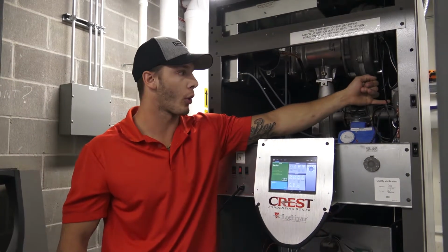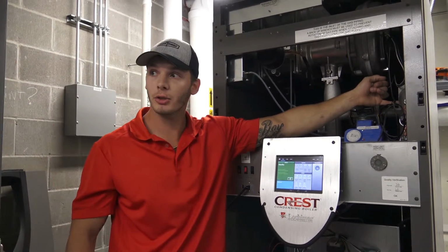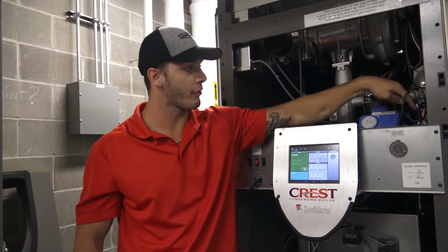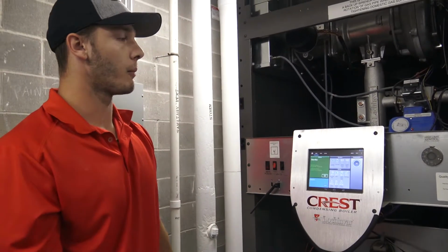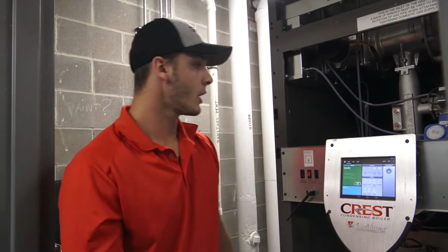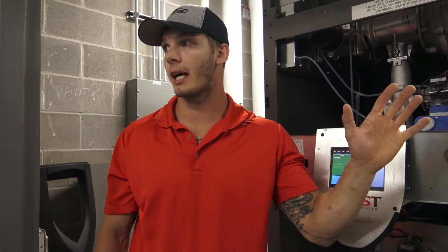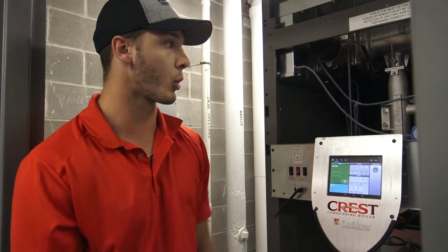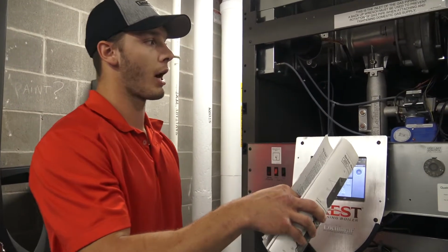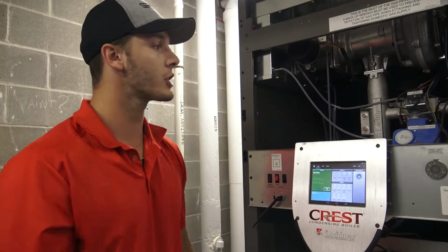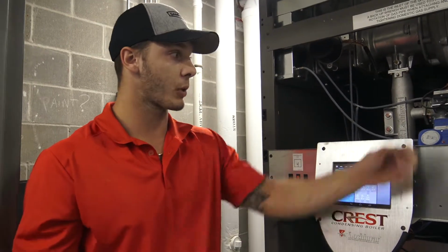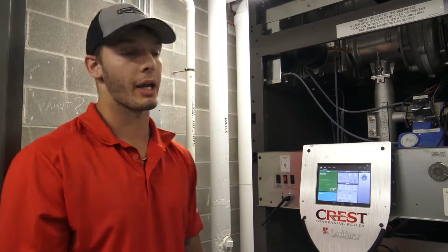Right here you're going to have your high gas pressure switch, and right here you're going to have your low gas pressure switch. Those are resettable? What's that? Are those resettable? Those are both automatic reset. Those are not manual reset. They have settings on them that are not meant to be changed. If it goes above 15 inches of water column, that switch is going to open up, and below 3 inches, the switch is going to open up and give you a fault on the screen. It's not going to say high or low. It's just going to say gas pressure switch failed.